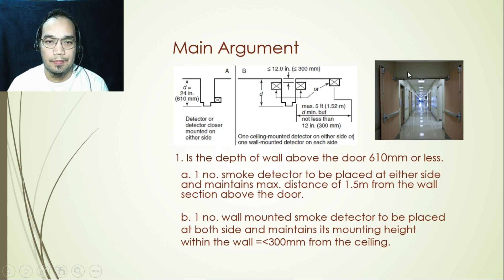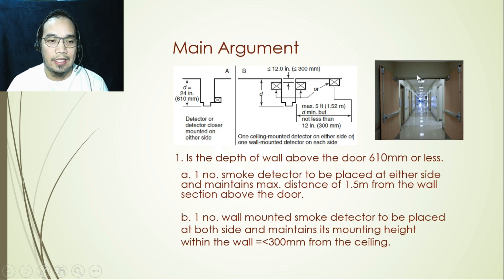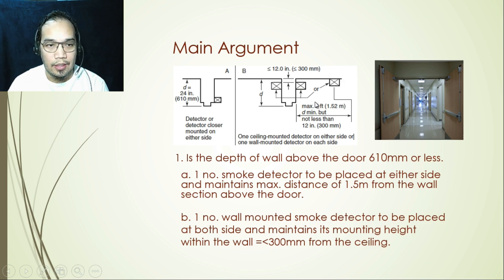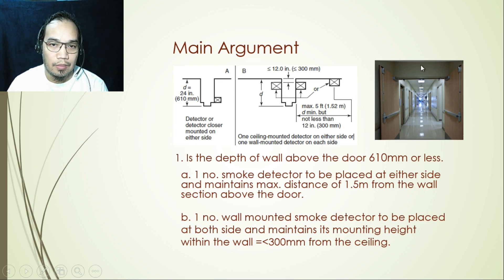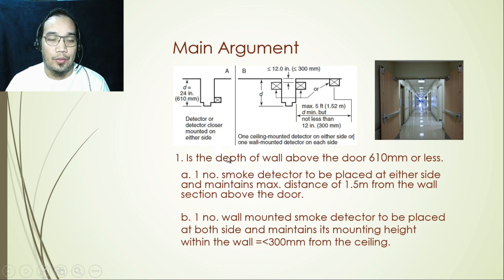The first case is when the depth of the wall above the door equals 610 mm or less. In that case, we only need to provide one smoke detector, placed at either side of the door, maintaining a maximum distance of 1.5 meters from the wall above the door. There is also an option to provide one wall-mounted detector on the other side, just above the door. However, option A — one ceiling detector — is preferable as it reduces cost.